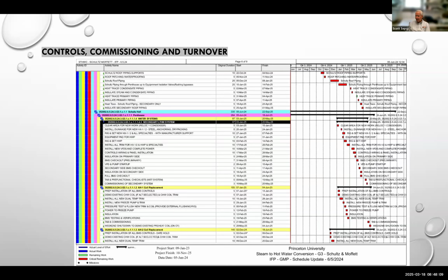before systems come online. And if you're getting new types of equipment like adiabatic humidifiers or equipment with new onboard controls like new brands of domestic water heaters, you have to engage early, getting design and submittal reviews to make these transitions smooth and timely. Review the installations, do it early in the commissioning process on site. Closely review the location of sensors such as differential pressure or coil temperature sensors, installed correctly, and you got the right coverage. We've had to replace sensors that did not cover coils adequately, so that's a lesson learned.